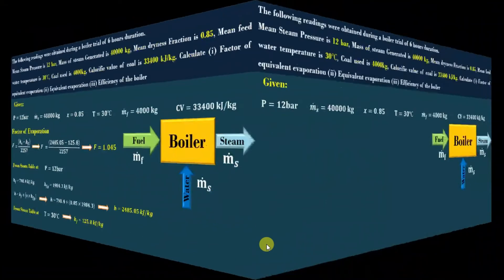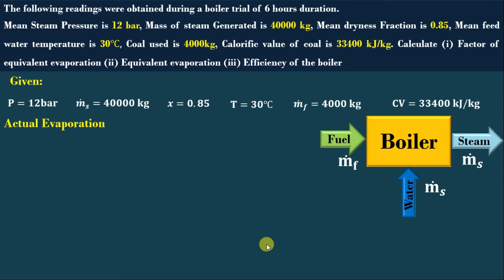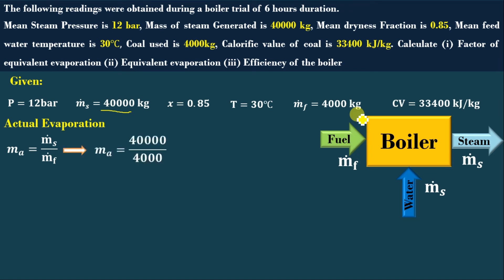Now we will discuss actual evaporation. The actual evaporation is the ratio of mass of steam generated divided by mass of fuel used, that is MS / MF. Mass of steam generated is 40,000 kg per 6 hours and fuel used is 4,000 kg per 6 hours. Substituting, the actual evaporation MA = 10 kg of steam per kg of fuel.